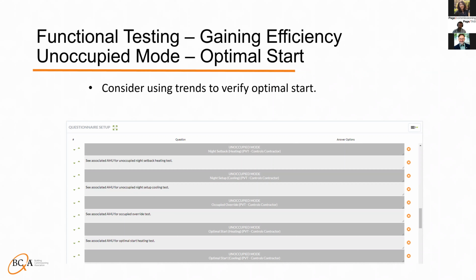which is kind of hard to explain, but let's say we're on site now and we start with the building occupied. Then schedule it to unoccupied about 5 minutes from now, then to occupied again in about an hour from that time. Once the building goes unoccupied in 5 minutes time, we adjust the space temperatures to extremely hot or extremely cold, but still keeping them inside the night setback set points. We do not want to go into night setback. We want to go into optimal start.